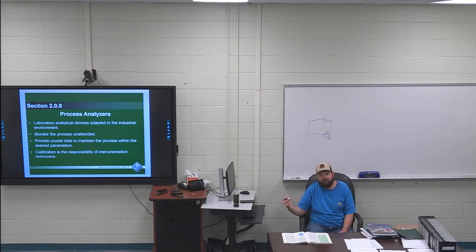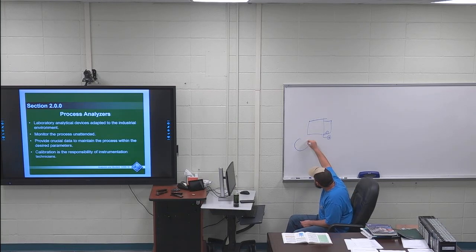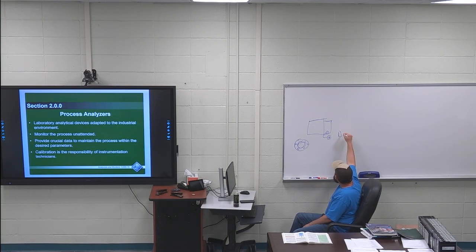And this might be where we've talked about stuff having a wet leg or a dry leg. I have come to find out that's a little bit of an old terminology thing. They're called capillary tubes, and what they are is just a tube filled with oil. They have a flange with a disc in it, and all you do is push on this and you're pushing on oil in the tube, and then you come down to a DP. So say you have an oil-filled line coming into here, and then your high pressure coming into here.